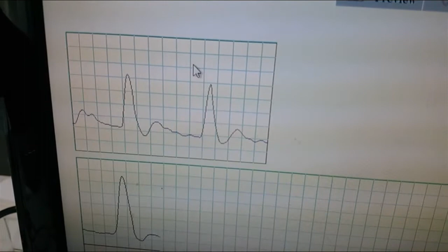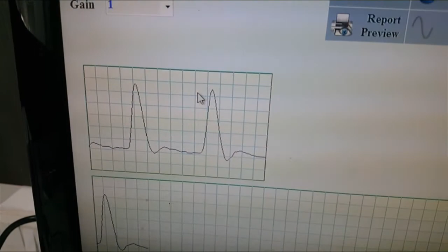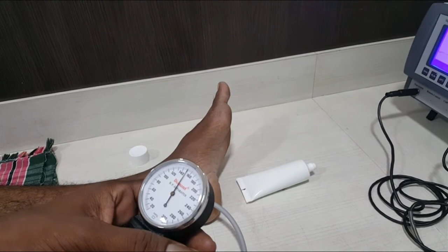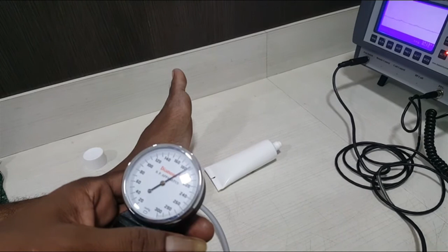Okay, so he has connected the cuff. Before that we have to record. Press recording. Now I am recording the toe pressure. Waveform is recorded. Now he is measuring the toe pressure. When you slowly deflate, you have to listen for the sound. You should also look for the waveform. Now you can see here.